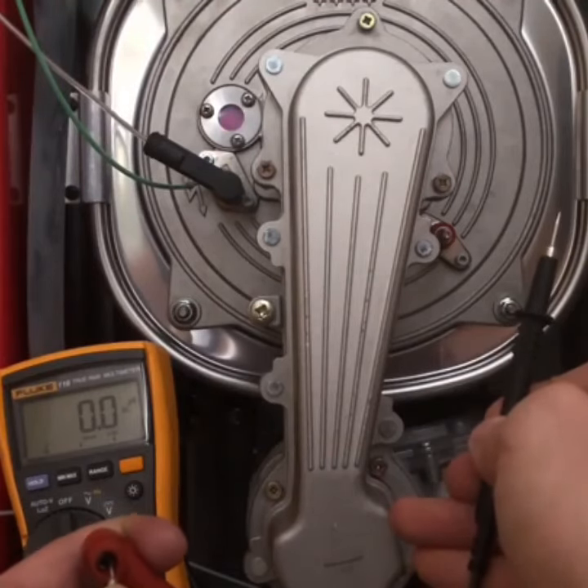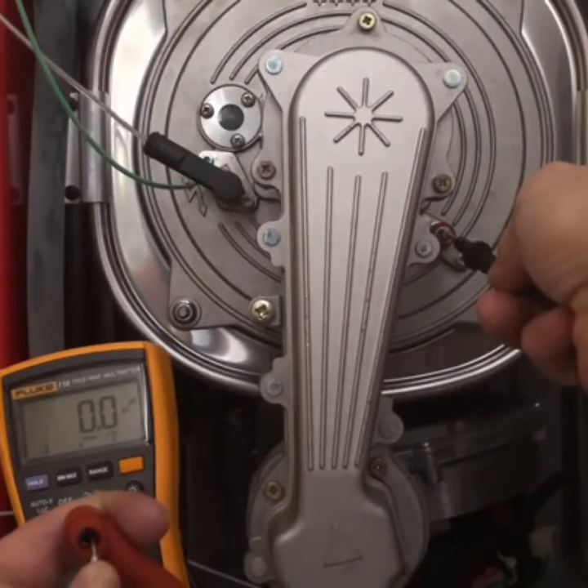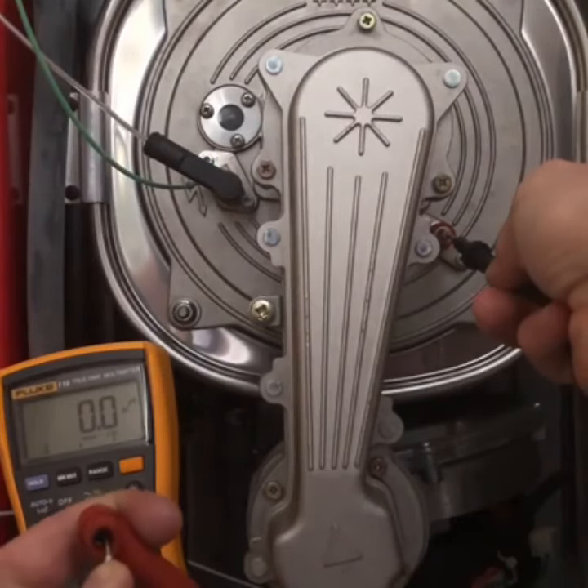If you're not getting the readings you expect, it could be that the flame sensor is faulty or that it's a bit dirty and it's insulated itself so it's not getting the proper readings.